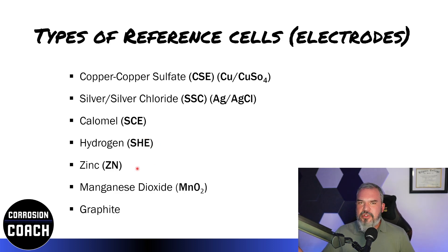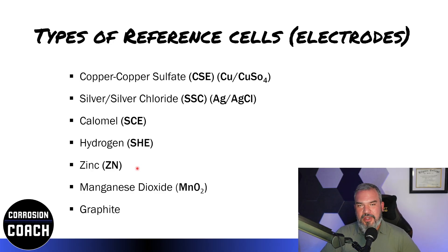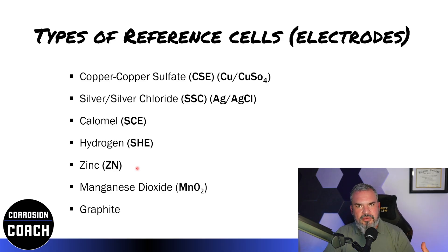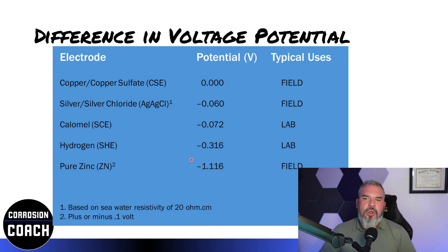Zinc — just the metal zinc — can be used out in the field. I've used one inside production tanks down the thief hatch where I can't use a copper sulfate reference electrode because the environment would contaminate it, and it would also contaminate silver-silver chloride. So zinc can be a very good tool in certain environments. It does have limitations, particularly with high temperature, but it can be used in the field. The other two on the list exist but are not commonly used.